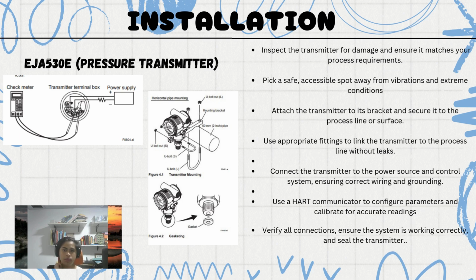Now I will talk about the installation of the EJA 530E pressure transmitter. Firstly, we inspect the unit itself to ensure that it is working. Secondly, we pick a good spot for installing because it is a very sensitive sensor. Third, we ensure the transmitter bracket is secured to the process line or a flat surface. Next, we use appropriate fittings because this has to stay in place and not fall down.